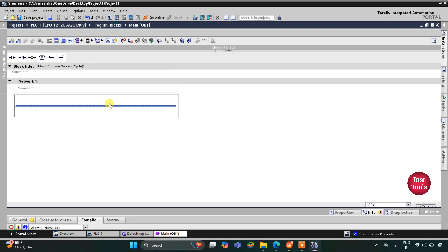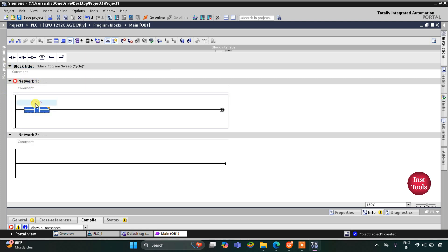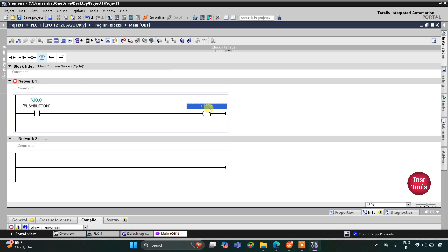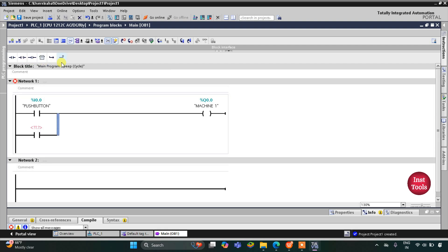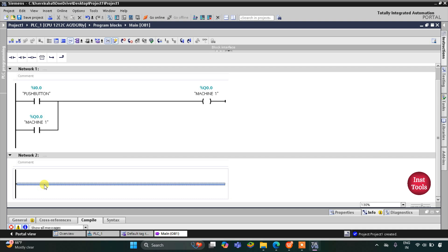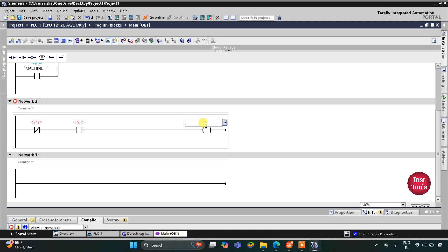We will go to program blocks and then Main OB1, where we will be writing a ladder logic for this example. First, we will insert a normally open contact for the push button and then insert a coil for machine 1. To keep machine 1 latched when the push button is released, we will open a branch, add a normally open contact for machine 1, and then close the branch. When the push button is released and machine 1 is on, a memory bit M0.0 gets activated.